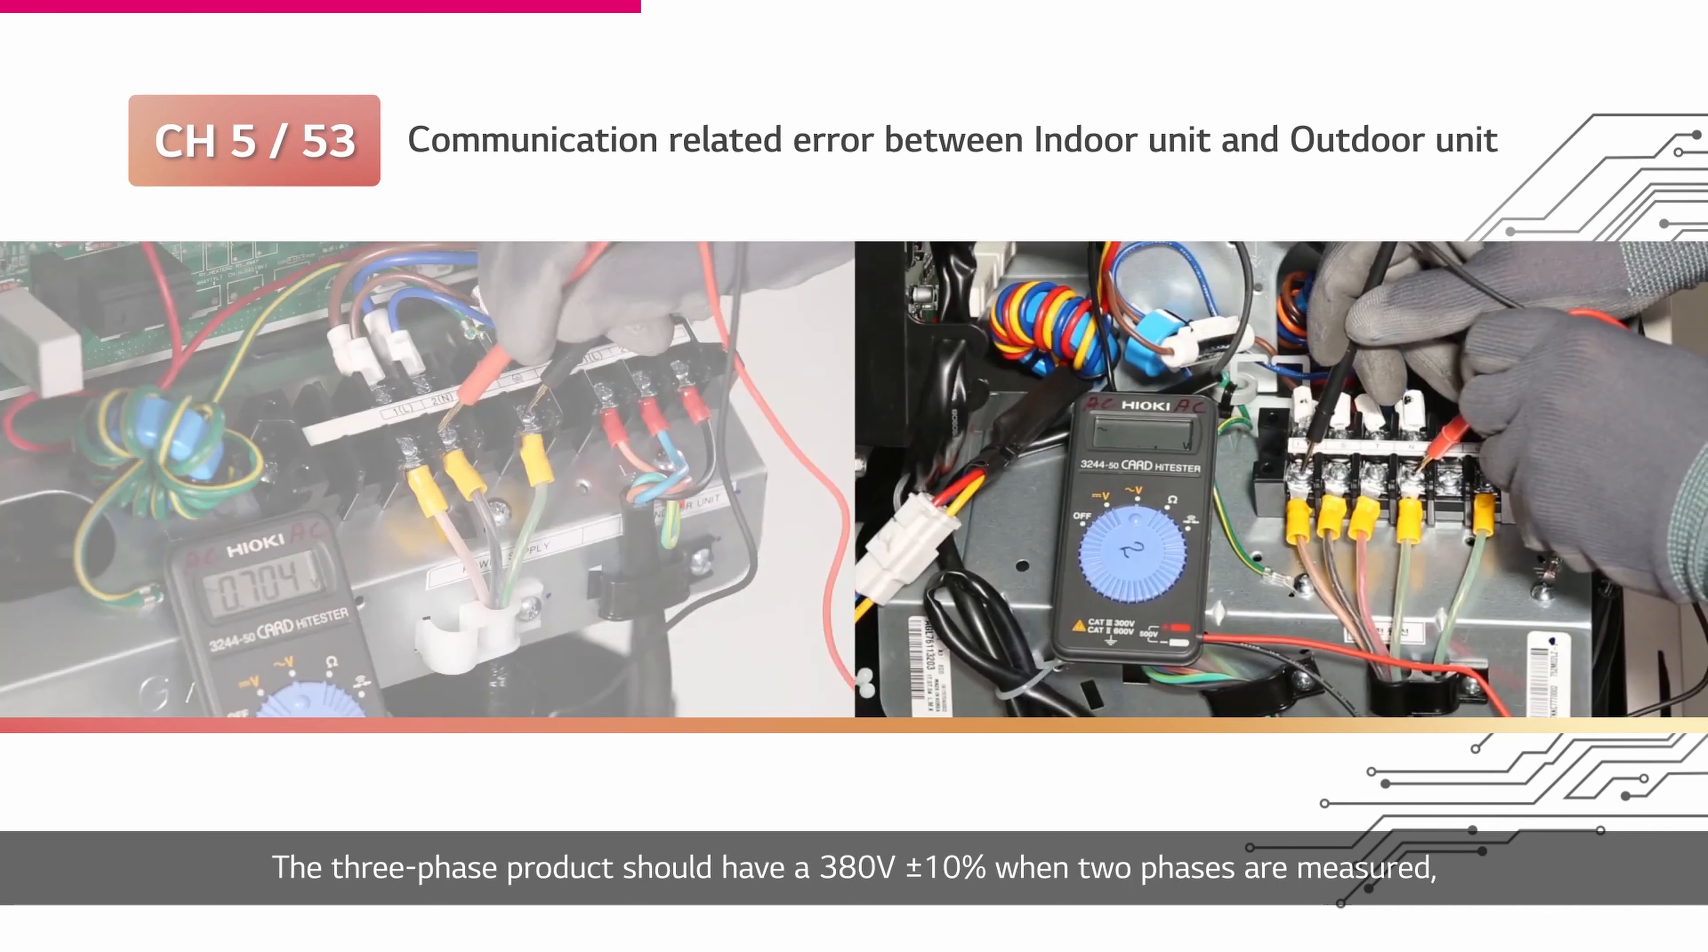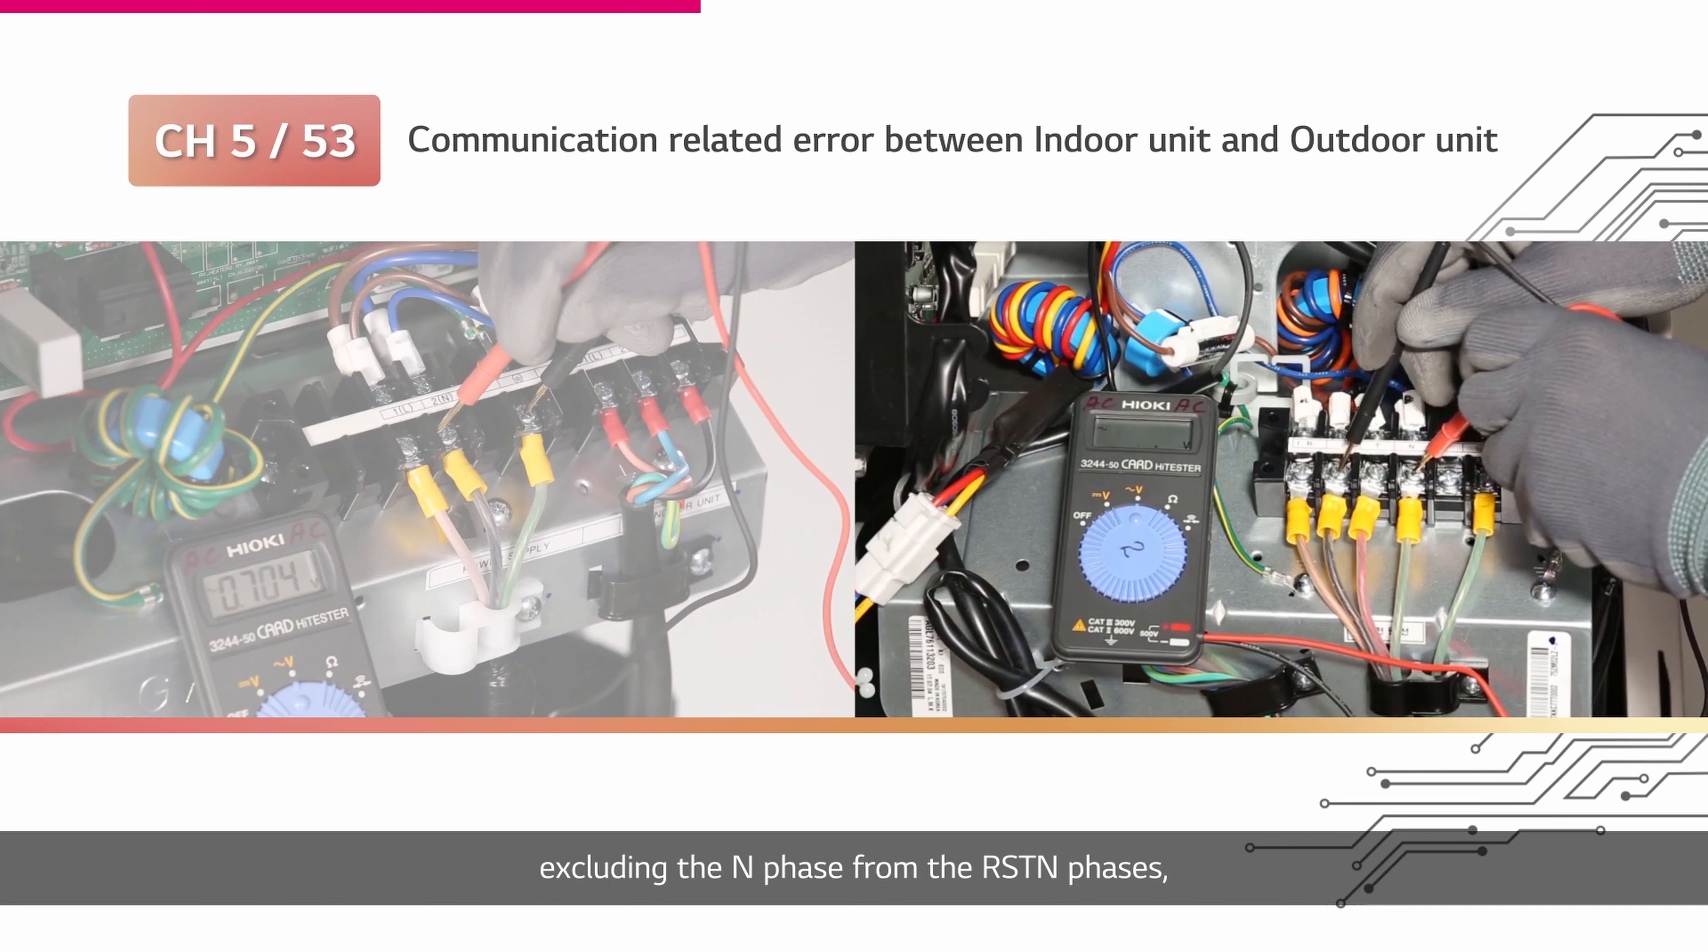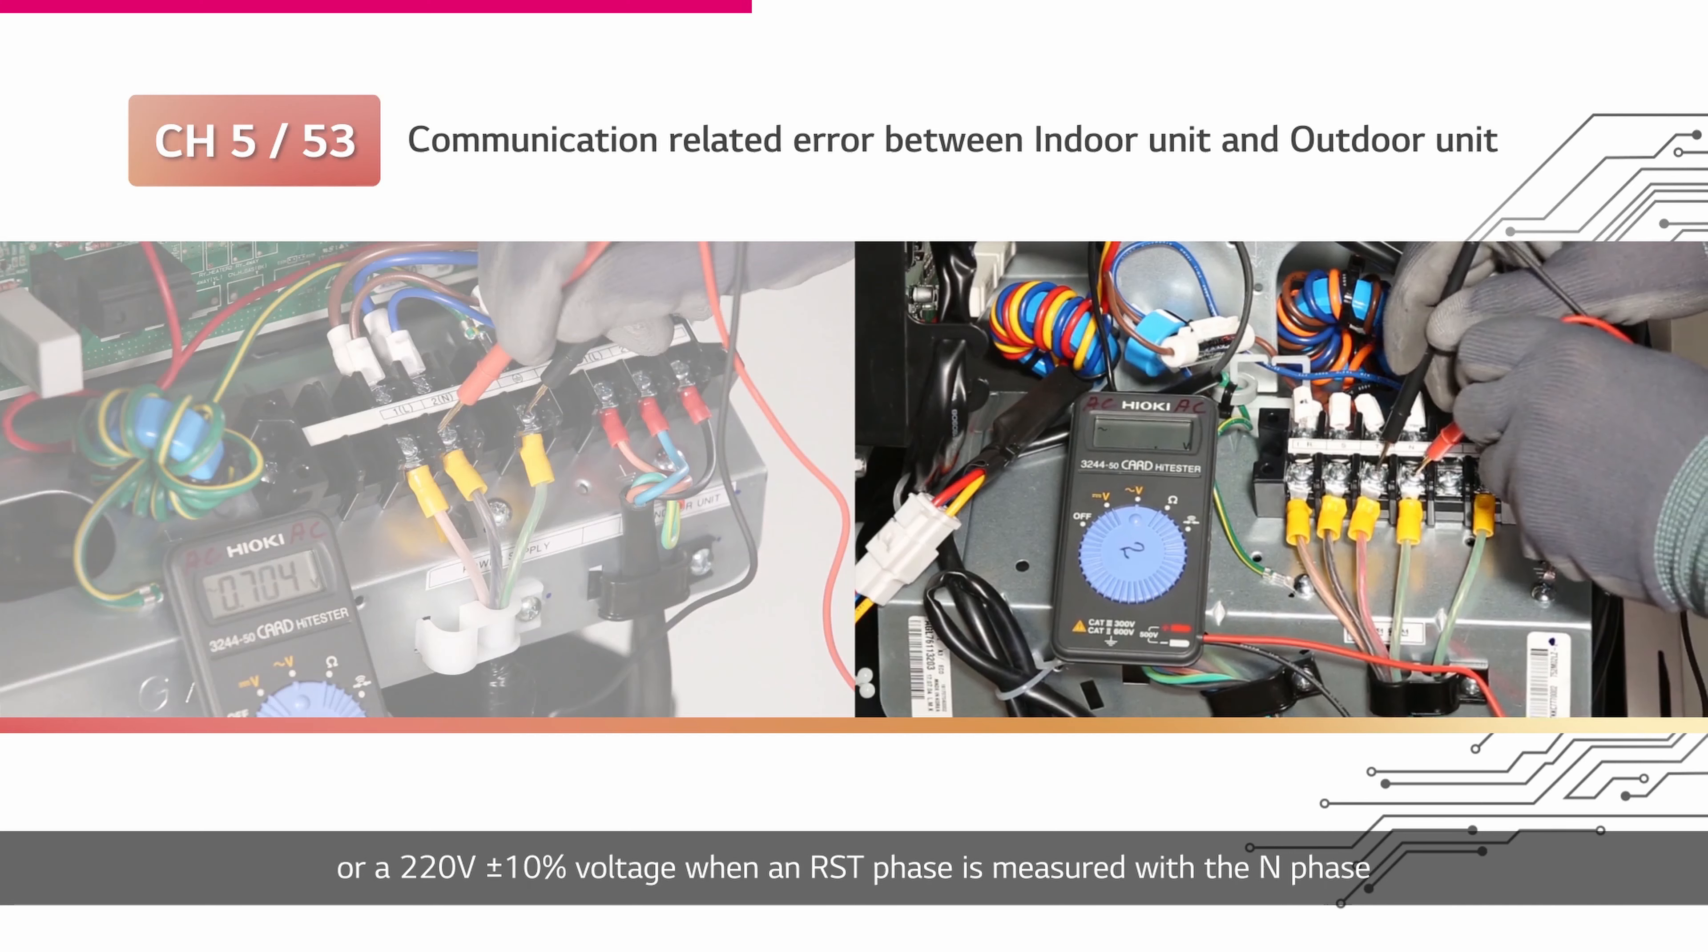The three phase product should have 380V plus minus 10% when two phases are measured, excluding the N phase from the RST N phases, or 220V plus minus 10% voltage when an RST phase is measured with the N phase.